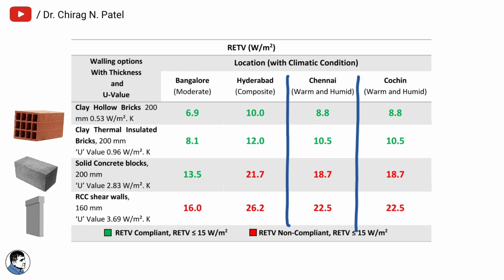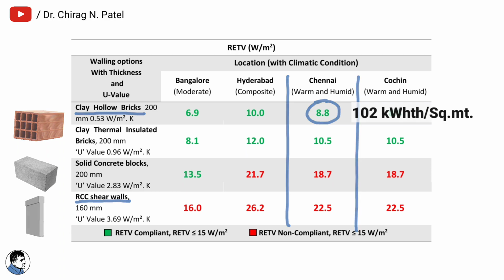From the study data, if we take the example of a building located in Chennai and compare clay hollow brick wall with RCC shear walls, the RETV of building with RCC shear walls is 22.5 watt per meter square, which is 187 kilowatt hour thermal per meter square of building built up area. The same with clay hollow brick wall is 8.8 watt per meter square, which is 102 kilowatt hour thermal per meter square of built up area. The meaning of that is what?